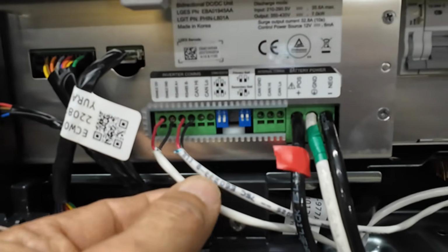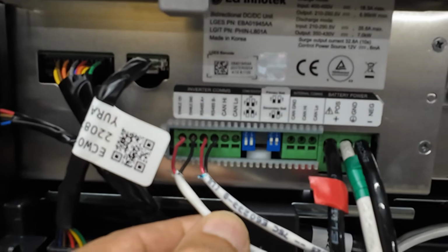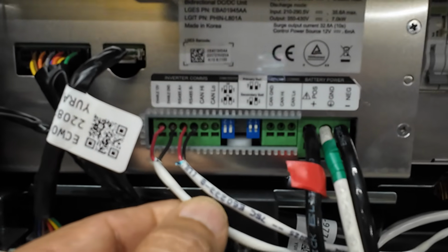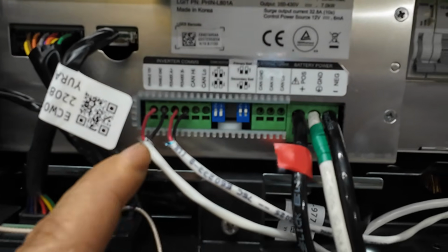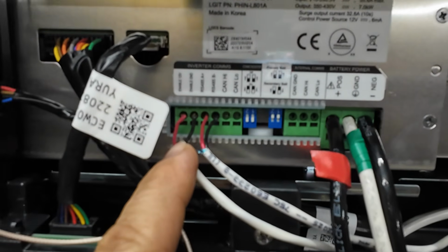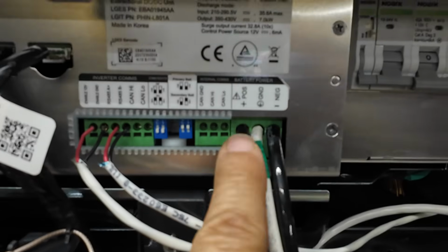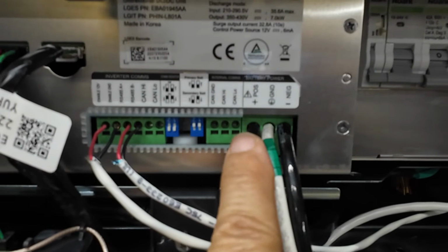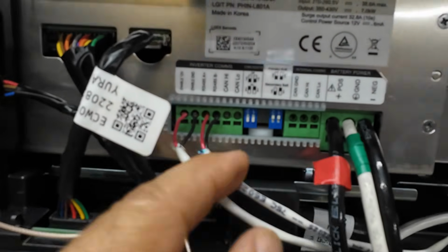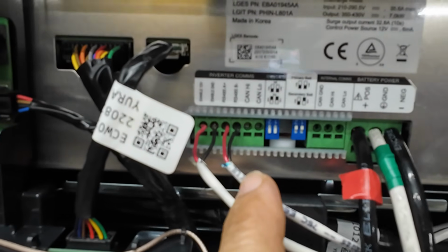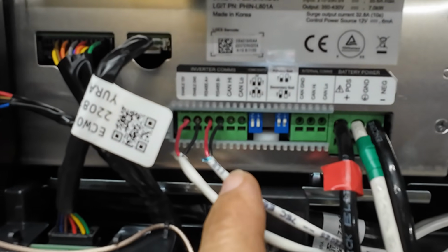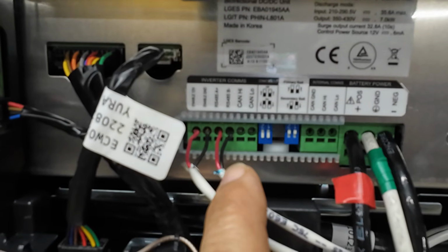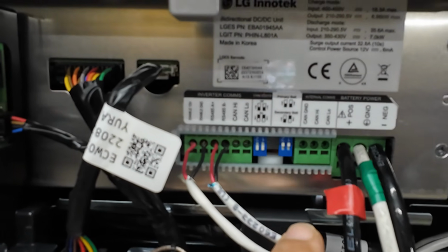One is an enable cable, which the inverter uses to turn the battery on. Without a signal on this enable cable, there's no high voltage coming out of these wires. The other one is for RS485 communications, which is how the inverter gets operating data from the battery.